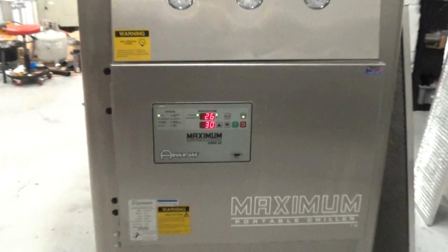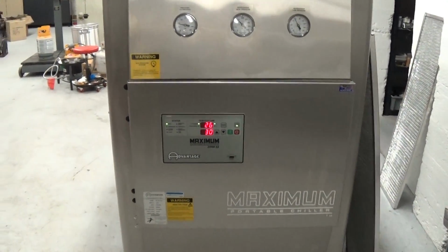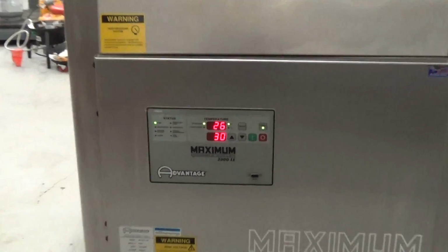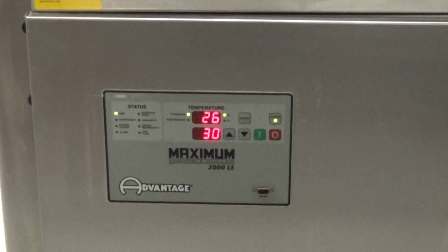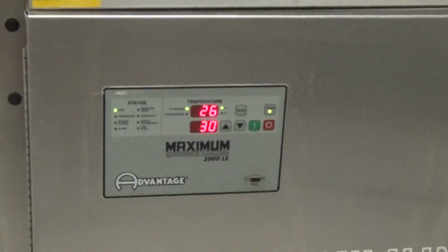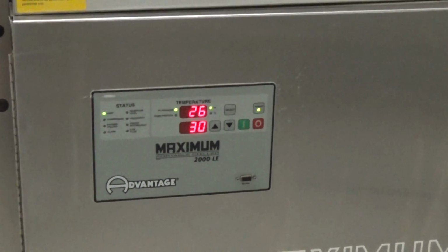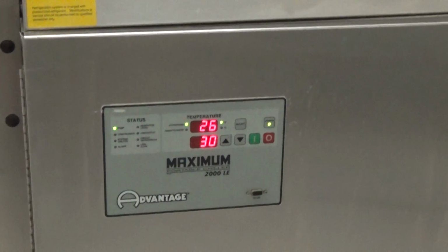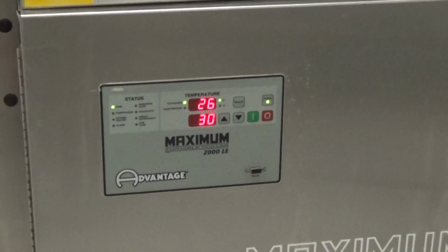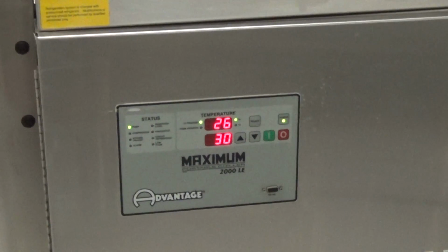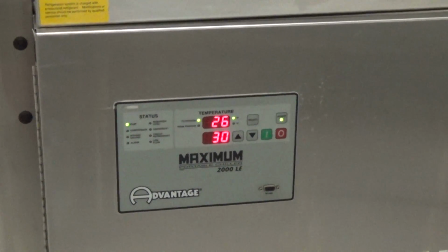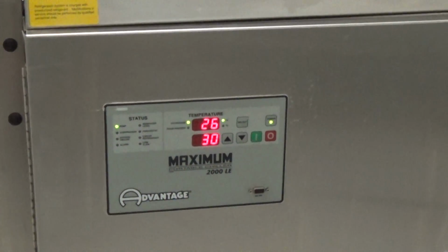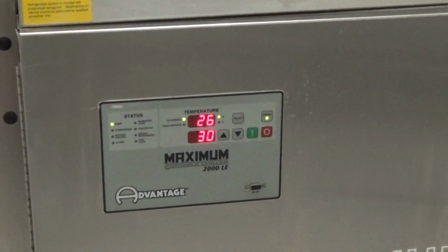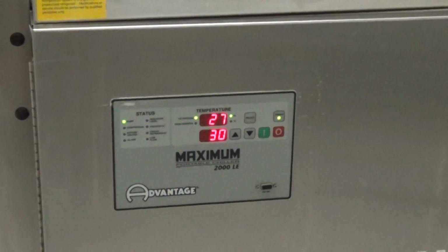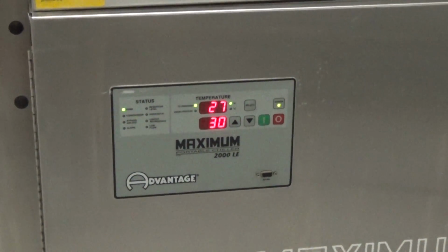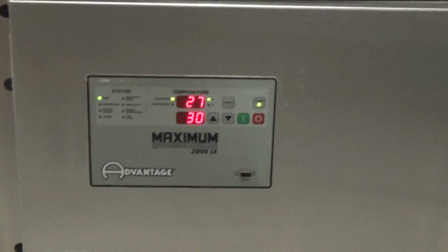We have customers who run straight water at temperatures sometimes in the 45 Fahrenheit range and so forth, and it takes a learning curve for us to educate them that yes, 45 F is not below freezing, but there is freezing taking place in your exchanger, and problems happen when people are running straight water at those temperatures. The point being, for this brewery application here, about 50% glycol mix, possibly 30. All the different types of glycol out there do have different ratings, so check that, and we can help you check that if you'd like.